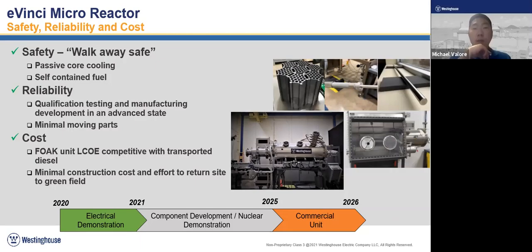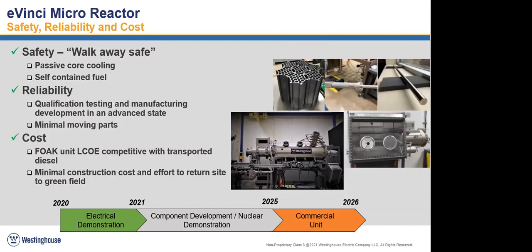It's a relatively small reactor, so load following is different compared to massive pressurized water reactors - that's a challenge. Really, I think we're limited by the remaining heat; there's such a large heat sink from the core and all the metal. That's what limits our speed coming down on load. Is that correct? That's correct, yeah.